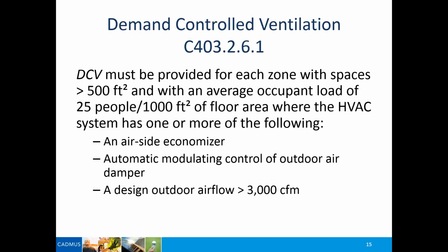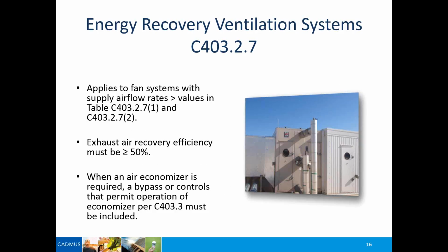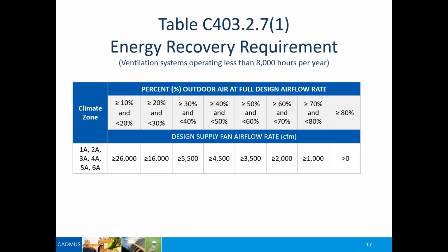What's different in this code provision, and I moved a slide, this just talks about the efficiency of the energy recovery ventilation system. It has to be at least 50% efficiency. I know that some of the above code programs right now are speccing about a 70% efficient energy recovery ventilation system. So 50%, again, is a minimum baseline code, but certainly you can get more efficient systems than 50%. Your next slide is probably going to be on enclosed parking garages, but I shifted that to the end of the ventilation requirements.